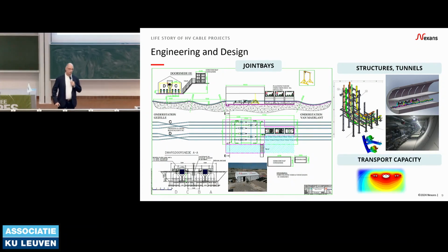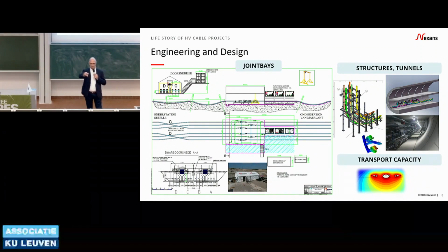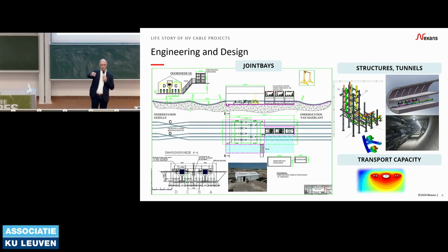And then we also have to cross-check the transport capacity. Not so long ago, we got a question from a Belgian TSO who asked us: I have 2 circuits, 2,000 square aluminium and 2,500 square aluminium above each other, 150 kV, I need that many MVAs, will it work? I have a doubt. And it was a real doubt, because it took us more than 2 months to recompute the admissible power in the link, the capacity in the link, because it was really, from a thermal point of view, quite tricky.